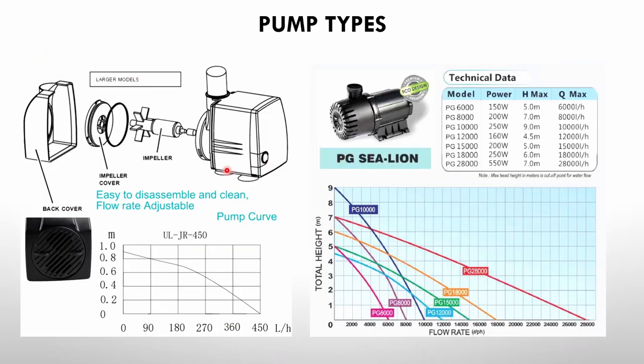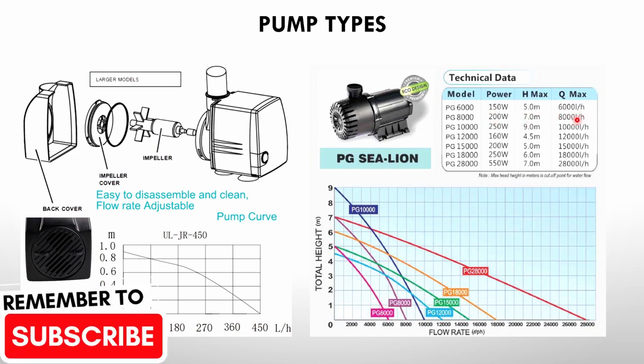Now I just want to show you one or two things here. This is a magnetic coupled impeller pump. You will see these pumps normally do not have a very high head, so if you've got vertical towers, in many cases they will not work. Here's a few pumps from this manufacturer. You can see the model numbers here, the power that they consume, the head, the maximum head that they can deliver, the certain liters per hour. So another thing that's important is the economy side of your pump. Maybe you'll get one pump that at 200 watts, 7 meters, can give you 8000 liters. The other one maybe only uses 150 watts for that same amount and head. So please have a look at the economy side if you select a pump as well.